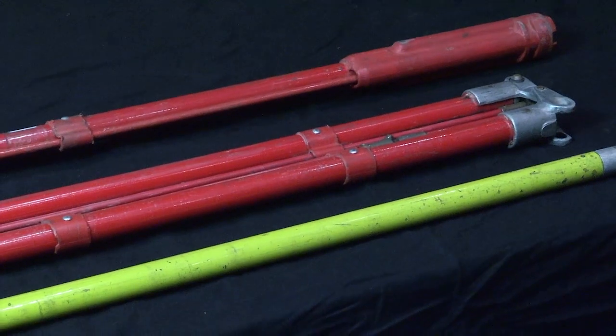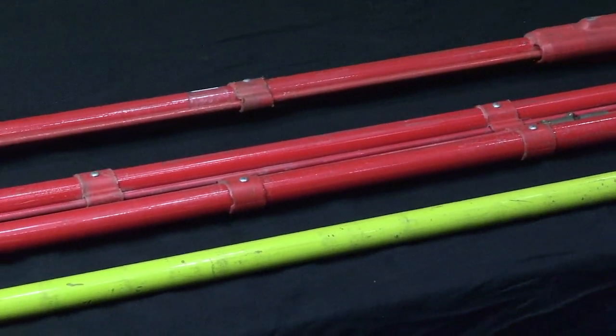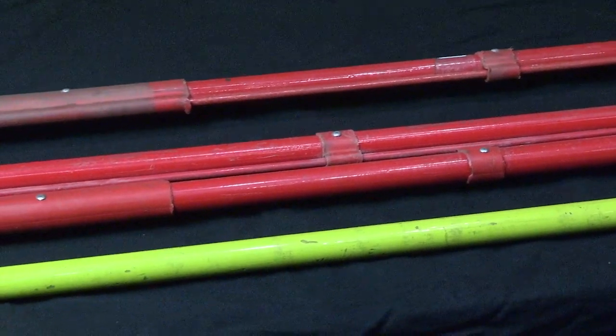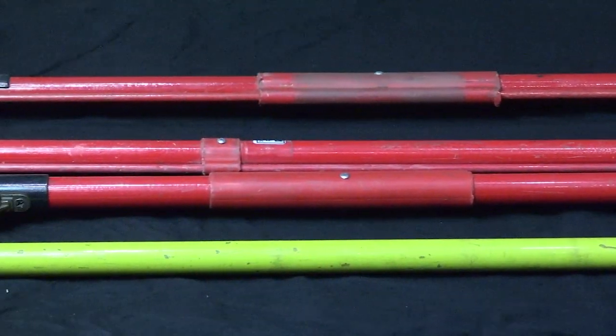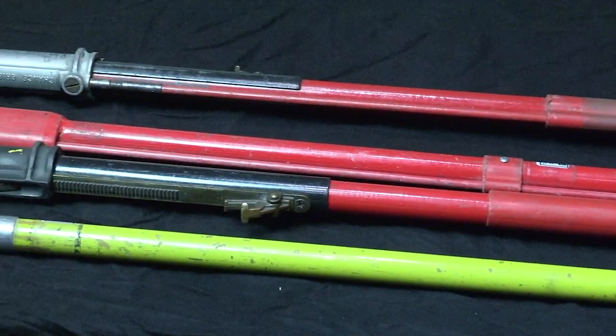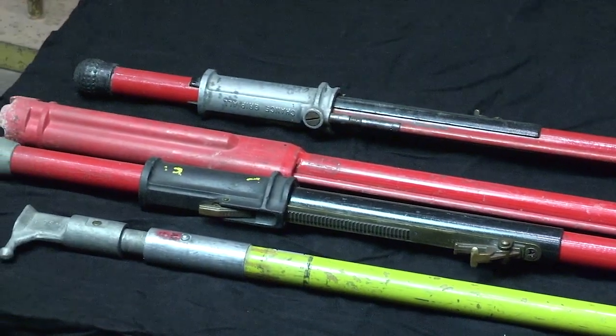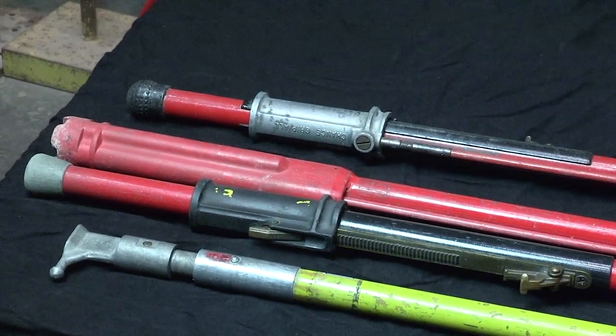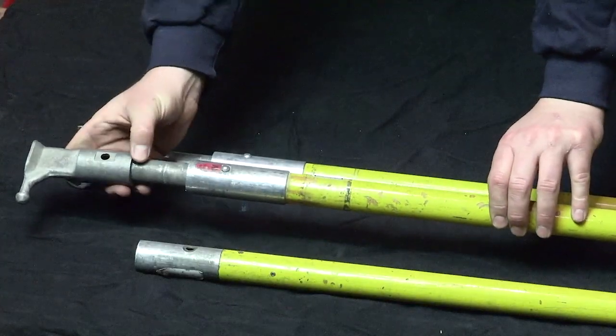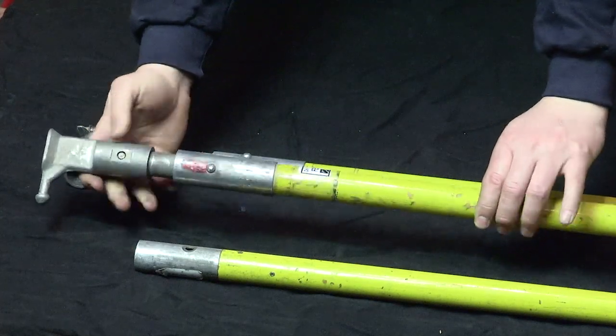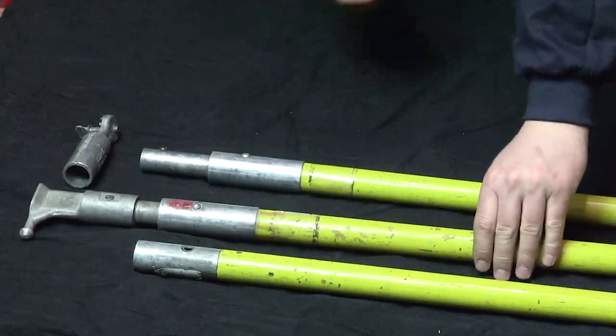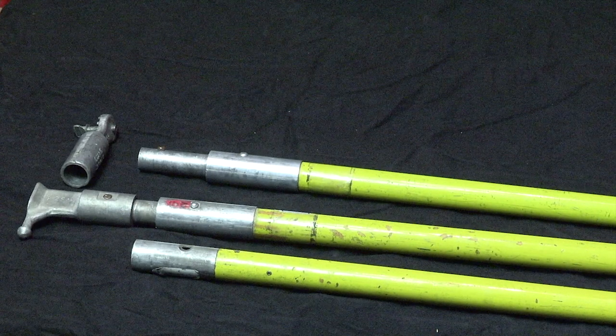A sectional P2 switch stick is equipped with a permanent top and bottom fitting. These fittings allow sectional sticks to be connected to one another to extend the total stick length if increased reach or work clearances are required. The fitting at the top of the stick supports various interchangeable heads. The most common head for a sectional stick is a P2 head. This head allows opening and closing of any hook stick-operated switch. When installing an MUS, you may use a sectional stick equipped with a P2 head to open and close reclosers, hang and remove tags, open and close low-voltage fuses, or operate single-blade or phase switches.